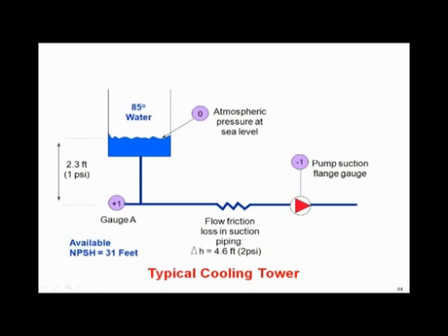Now what happens when I turn the pump on? Well, I've got this friction loss of 4.6 feet. By the way, I think everybody knows this. 2.31 feet makes a pound of water specific gravity one. So when I turn the pump on, my suction gauge on the suction side of my pump is going to become slightly negative. It's going to lose 2 pounds because of friction loss. So I have a positive pressure of one from the elevation. I lost 2 pounds running through the friction. So the suction gauge now reads a negative one if it's a compound gauge. It's one of my pet peeves. Everybody listening to this, make sure all your cooling towers have a compound gauge. It's not unusual. First they go on the job site and we see a gauge reads zero because it's not compound. And yet it may actually have a negative pressure with people telling us the pressure is zero.